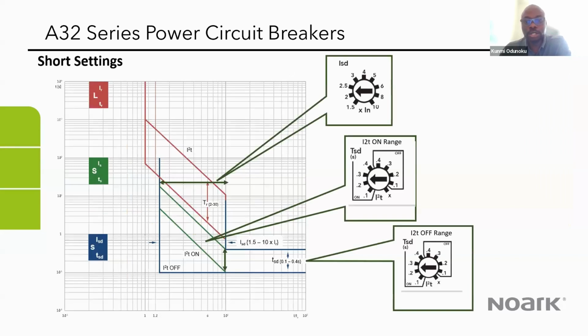Then we have the short time setting, which again is useful for coordination studies. Whenever you're doing some kind of coordination study, you want to introduce delay in different feeder circuits or sub feeder circuits. So this is the sort of settings you need for the air circuit breaker.